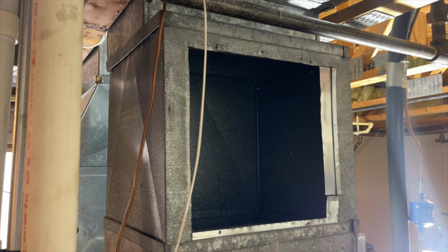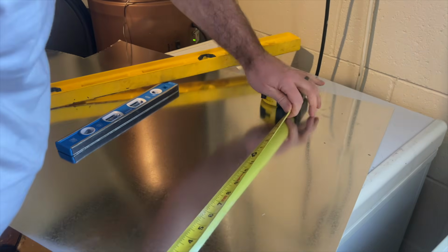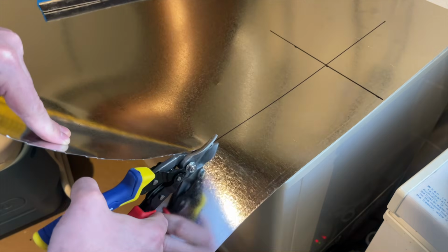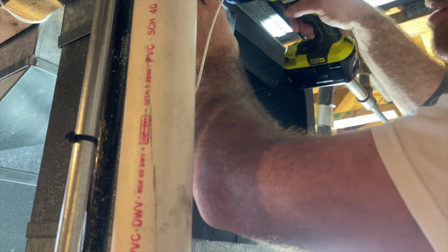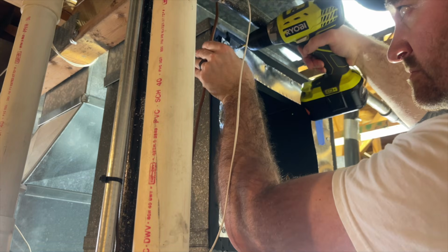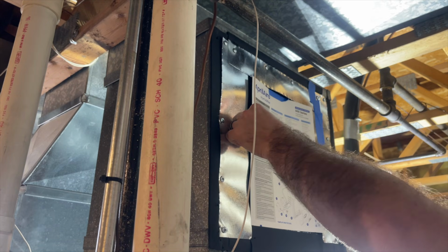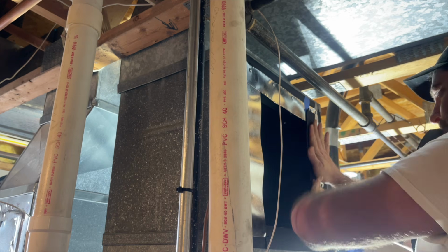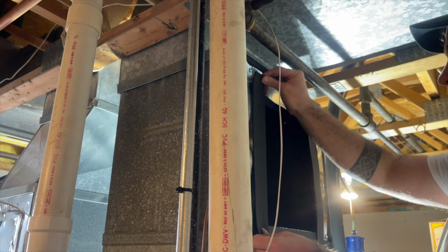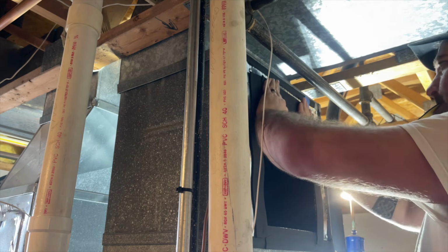Next, you can see the hole from the previous humidifier is significantly larger than what we need. So we'll measure and cut strips of galvanized sheet metal to size and then attach them the same way, filling the space so the hole is the exact same size as the template. Now everything is to size.